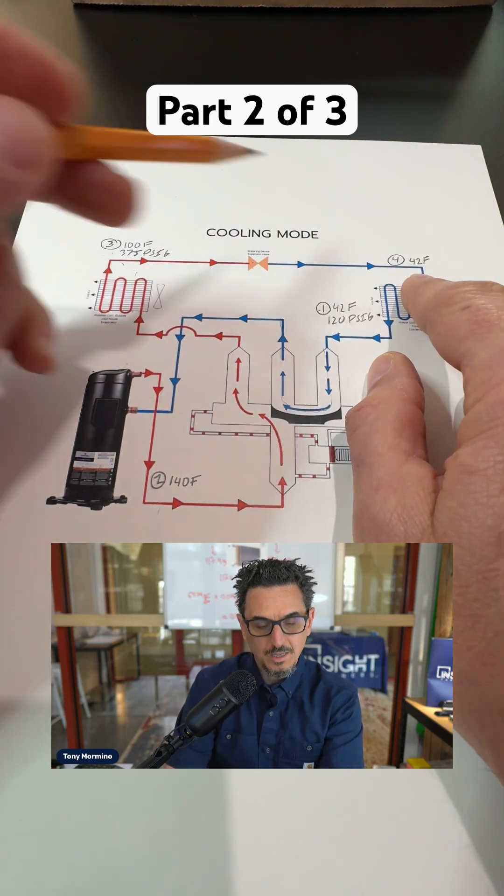The high side of this particular type of system is about 375 PSI. Of course, that varies. Then we go through our pressure drop device, which lowers the pressure and temperature of the refrigerant down to about 42 degrees.